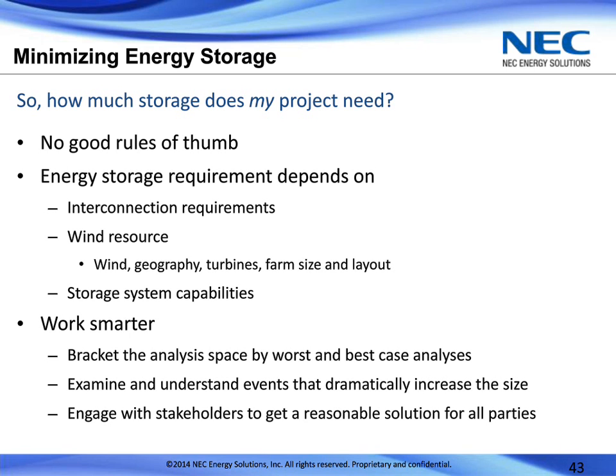The requirements placed on the energy storage vary from the regulatory type requirements, so in this case, the interconnection requirements, the ramp rates, also fault responses and transient responses, but also the underlying wind resource. What's the nature of that wind resource? How many turbines do you have in this facility? How are they spread out across the site? In this case, we had a single line of wind turbines that ran perpendicular to the prevailing wind, so you could expect a fairly high degree of correlation between those wind turbines in the event of a wind drop. On a larger facility, it takes time for a wind drop to pass through the facility, so you don't tend to see as dramatic a change.